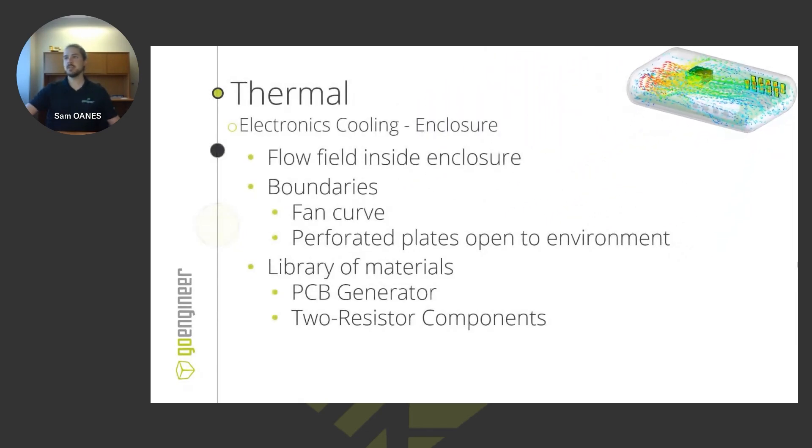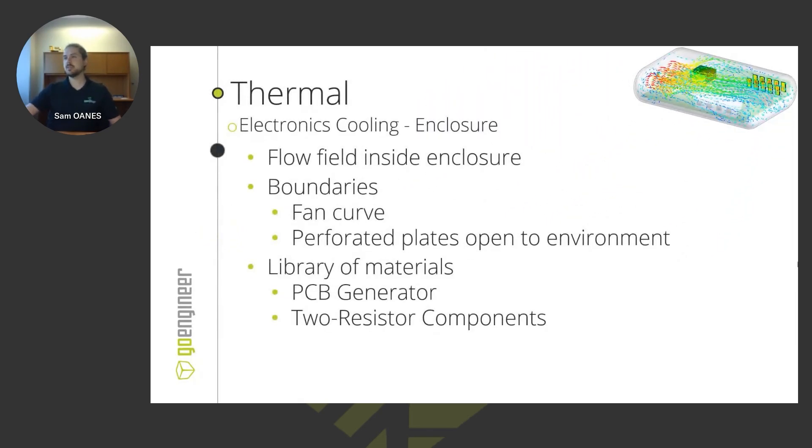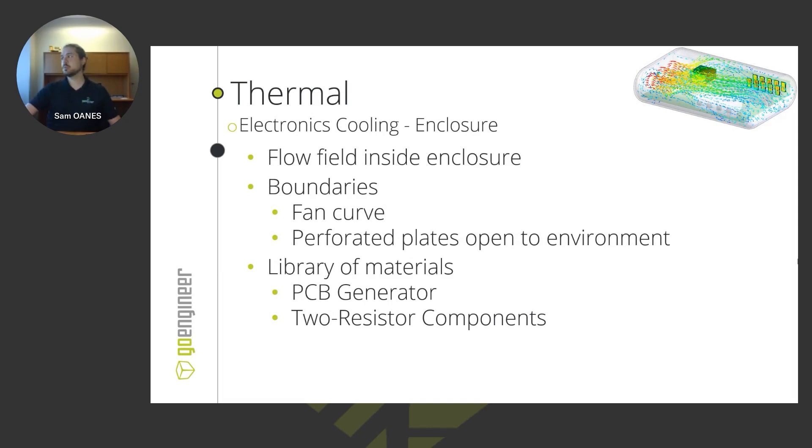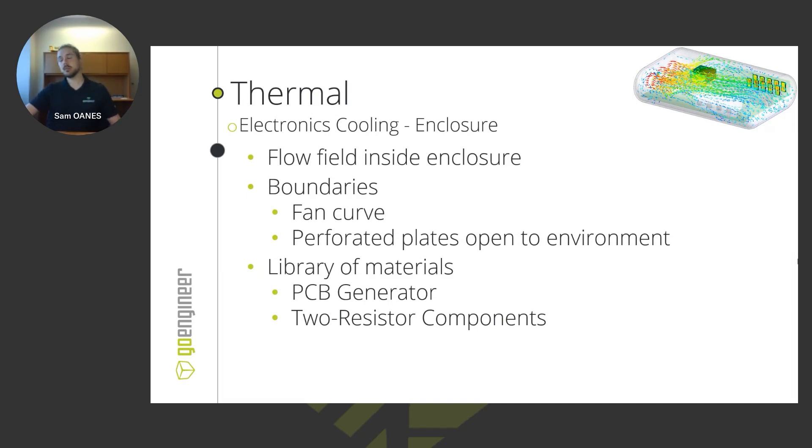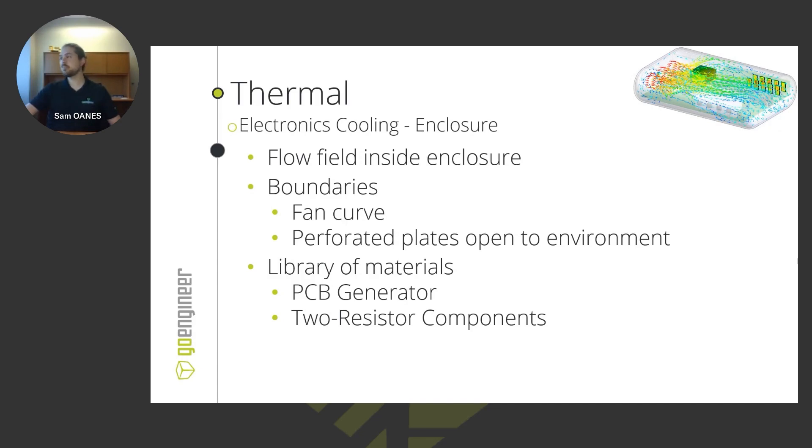The way that we set that up is we define a flow field inside the enclosure. This is what we call an internal fluid problem, where we're not considering the air outside the enclosure. That means we need to define boundaries where that internal domain is going to be interacting with the external domain. At the inlet, we define a fan curve as our inlet condition, pulling that ambient air into the internal domain with a fan.